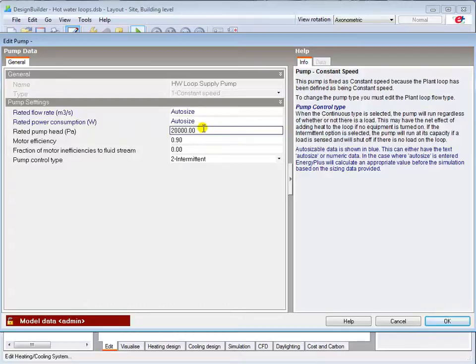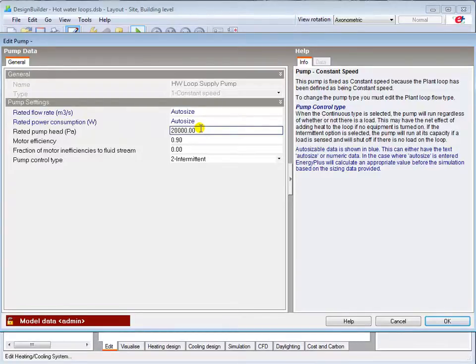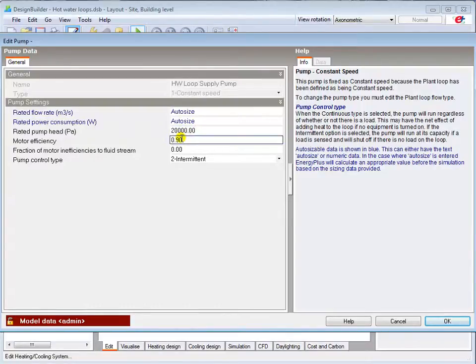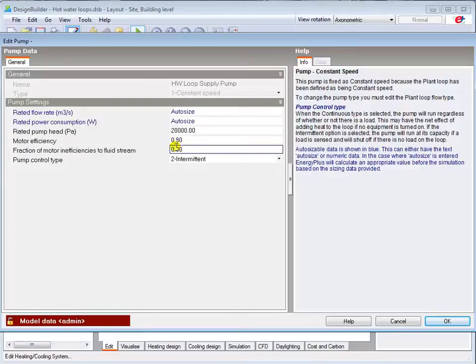If the variable flow option is selected, the resistance will be modified according to system curves to determine the energy consumption at each time step. Unlike fan motors, a pump motor is normally located outside the fluid flow, so there is no heat transfer between the motor and the fluid, hence this default value of 0.